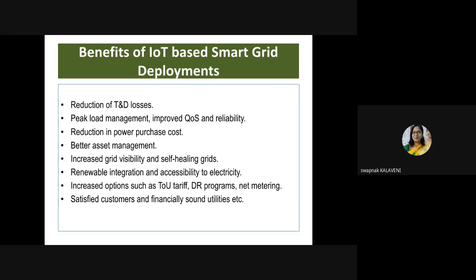Here you can see the benefits of IoT based smart grid deployments. First, the prime objective is reducing the overall transmission and distribution losses. How is it possible? Since you are continuously monitoring the elements present in the transmission system and distribution system, you come to the conclusion where the losses are happening, where they are at a higher level, and where they are at a lower level. So you have to give more focus to high loss areas, where you can introduce elements to control the losses, and take appropriate actions to control them. Thereby, on average, overall, we can reduce the T&D losses.